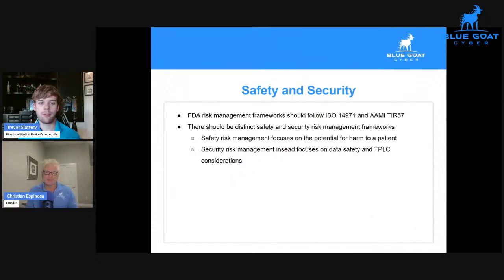All right, so there are a couple of different frameworks and different considerations when looking between safety and security. Under the context of FDA risk management, so what the FDA wants to see for a medical device, the two critical risk management frameworks should be ISO 14971 for safety risk management and AAMI TIR57 for security risk management. These should be distinct processes, meaning you can't just have one risk management framework to dump any problem into and get the appropriate outcome. There should be a safety risk management that's focused on the potential for harm to a patient, and a security risk management, which is focused more on data safety and total product lifecycle considerations.